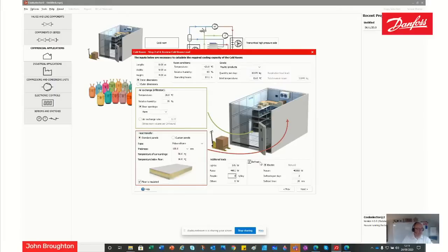It will be electric defrost. Now, again, if we are taking it at 15 degrees and taking it down to minus 25, that's a process. So there might not be any defrost time during that. Again, we need to know that when we talk to the customer, exactly how he's expecting to use his system and how long his pull down time is going to be. At the moment, we don't know that. So we'll leave the defrost load in there for now.